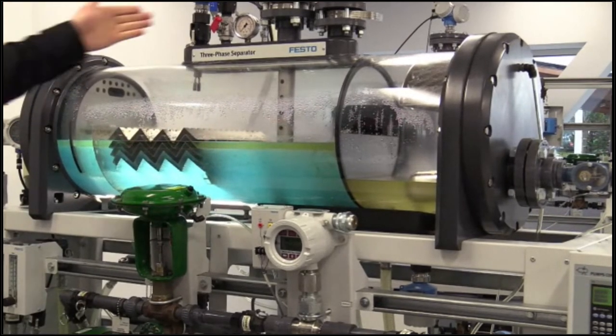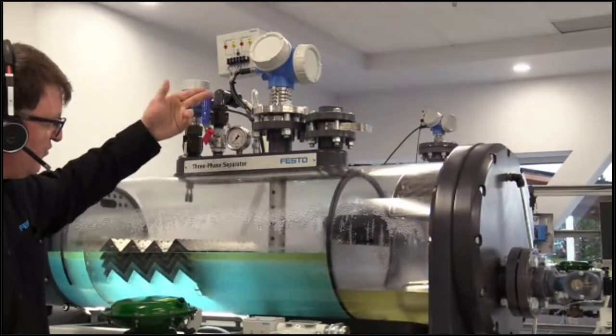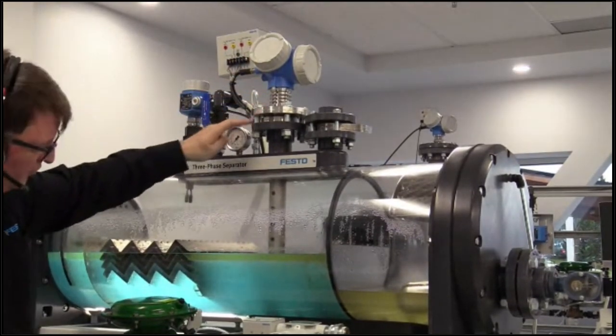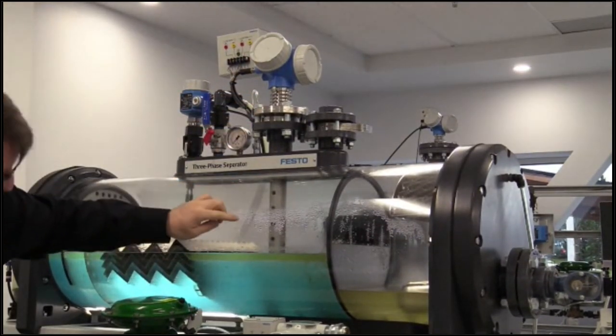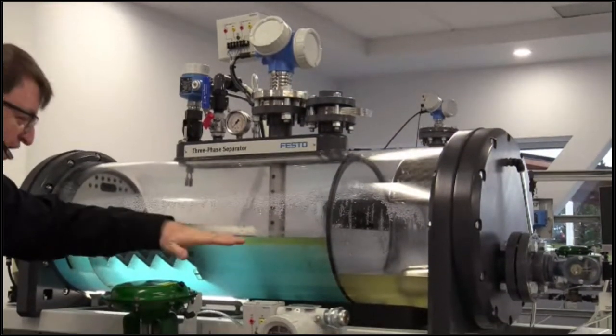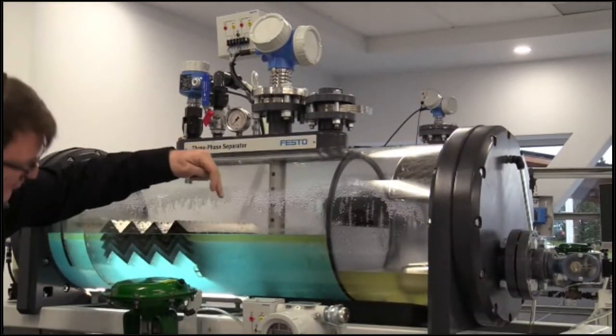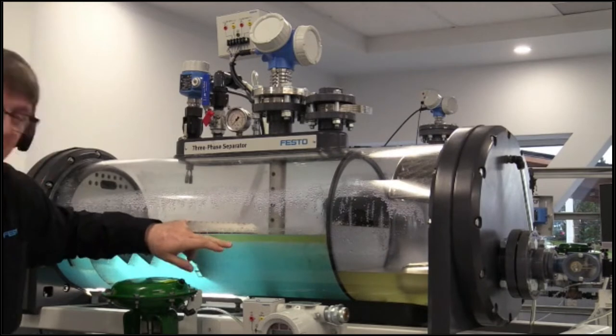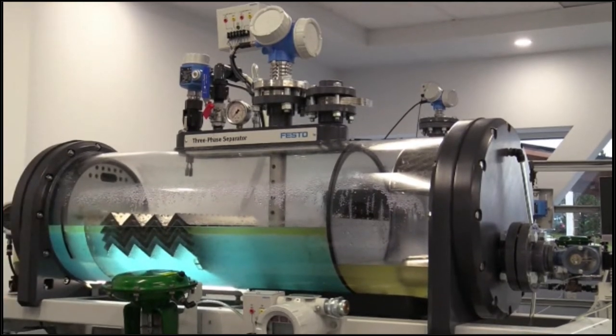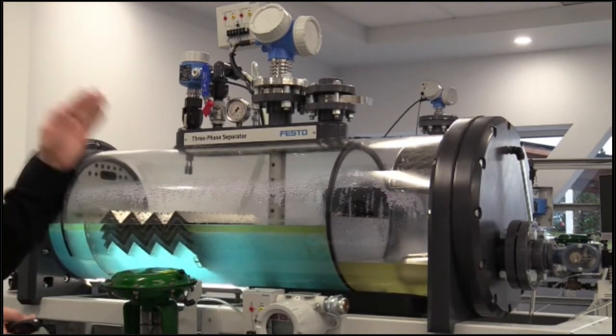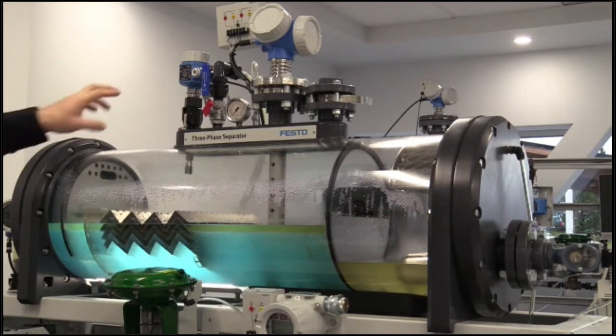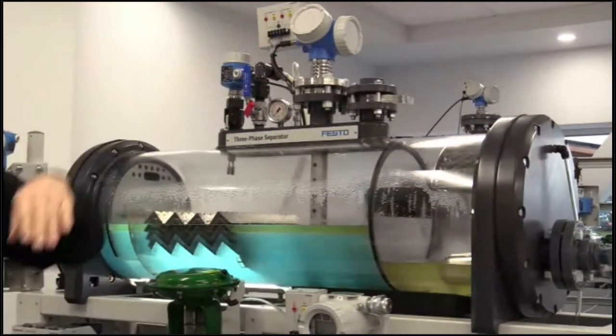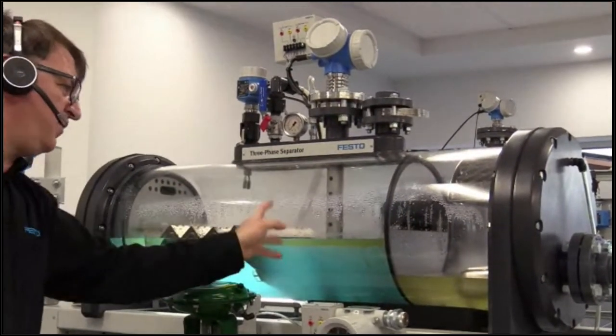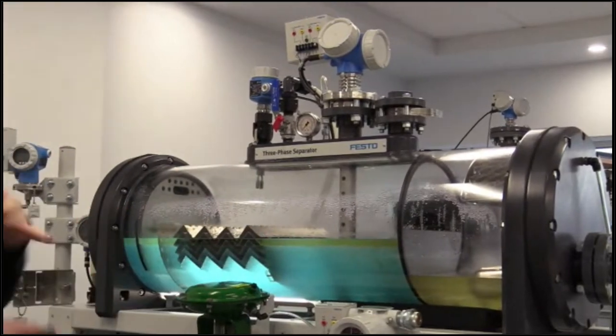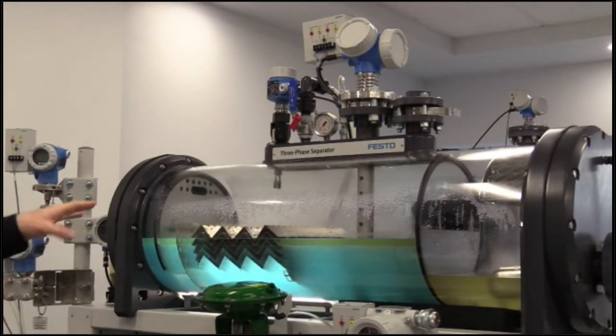So the radar is this device. What it's going to do is send a pulse. The pulse is going to be reflected as an echo in the first surface. It's going to continue traveling to the second surface, that's the layer between the water and the oil, and come back. So with one single device, we're going to have the two levels. So we can know exactly what will be the mix, the amount of oil and water present in the system.